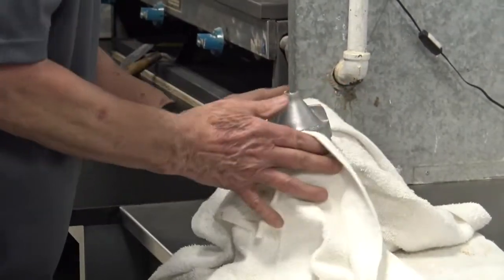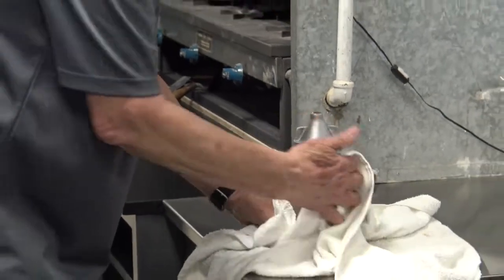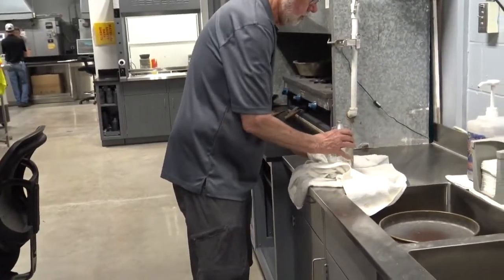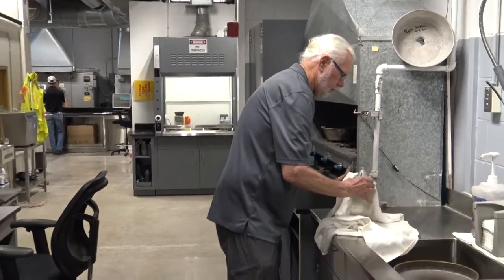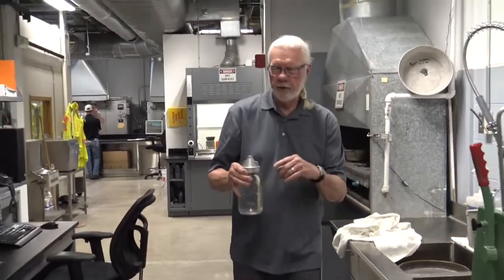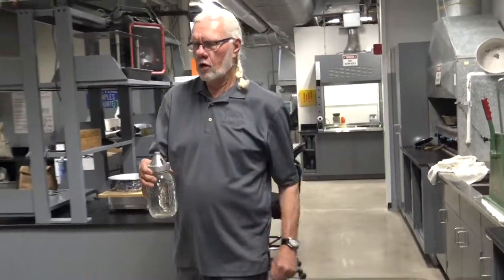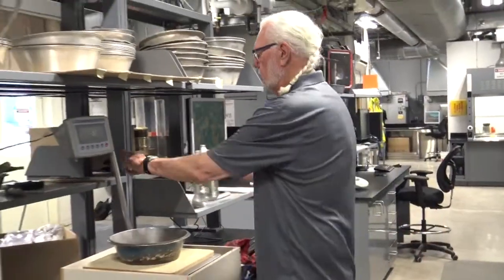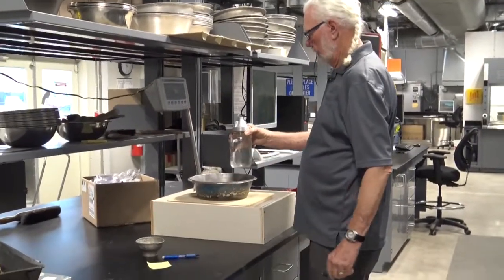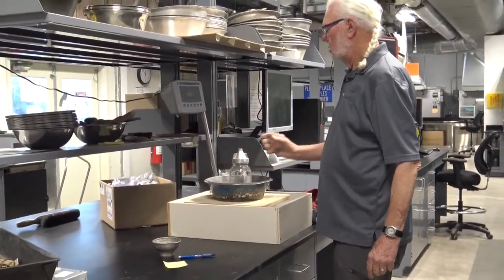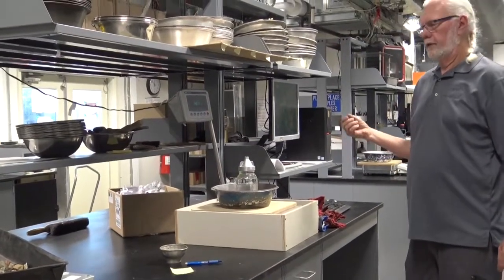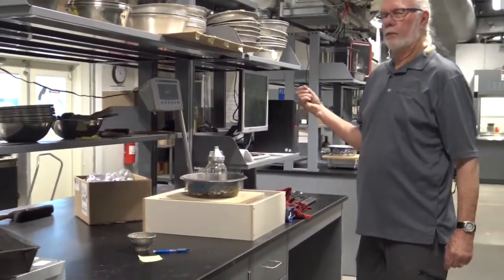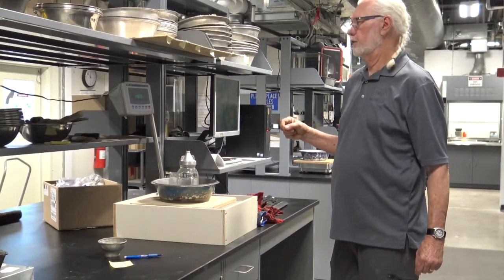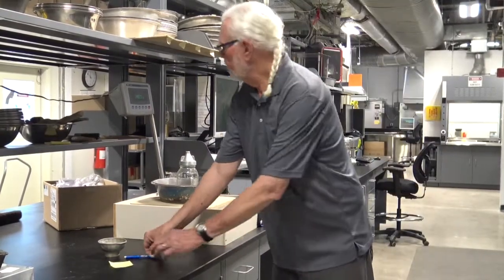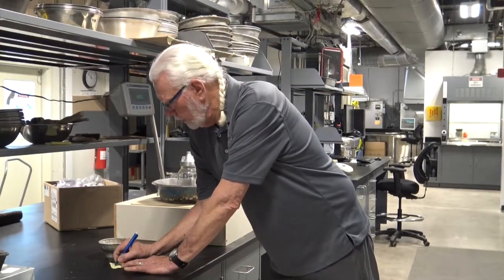Once we have established, we have our jar full of water, the calibration process, we then need to dry off the jar completely, making sure we get any water around the rim, making sure that the jar is sealed, and tare the scale. Then this weight will be the calibrated pycnometer weight that we need in our calculation to determine specific gravity. In this case, it happens to be 1,482 grams. So I just record that.